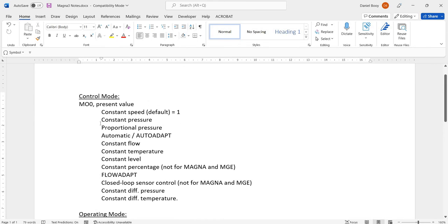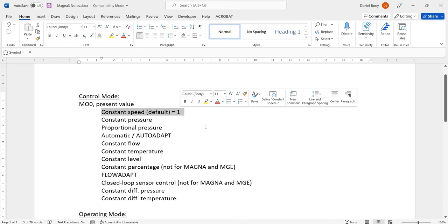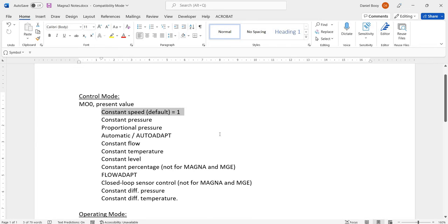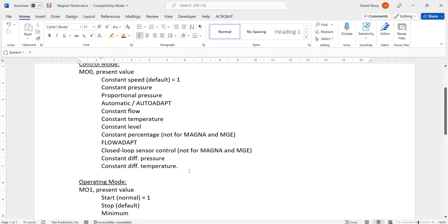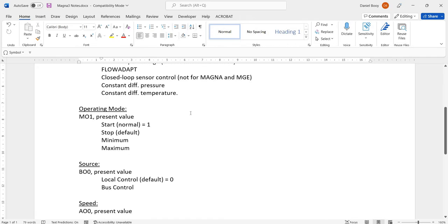Control mode on the pump, MO0, we need it to be in constant speed, which is counterintuitive because we're actually going to be driving the speed of it through BACnet, but that's the setting we need to give it. Operating mode, MO1, start is a 1, stop is a 2.